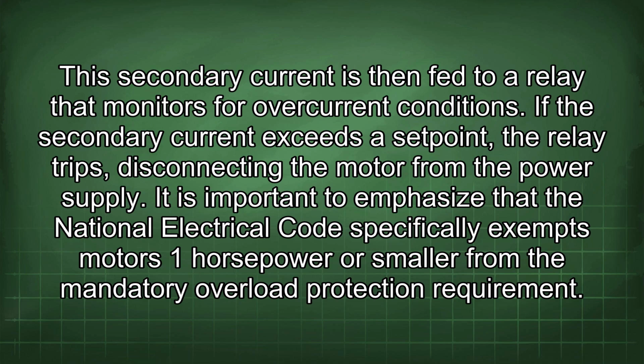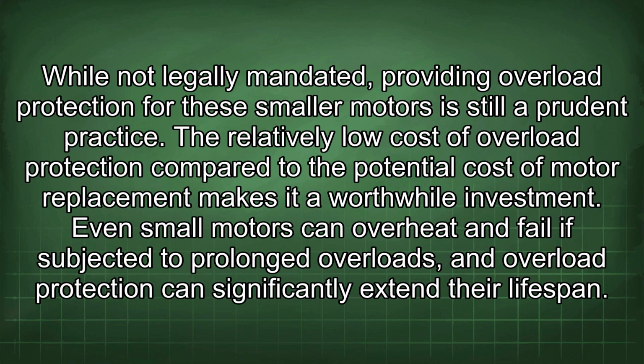It is important to emphasize that the National Electrical Code specifically exempts motors 1 horsepower or smaller from the mandatory overload protection requirement. While not legally mandated, providing overload protection for these smaller motors is still a prudent practice. The relatively low cost of overload protection compared to the potential cost of motor replacement makes it a worthwhile investment. Even small motors can overheat and fail if subjected to prolonged overloads, and overload protection can significantly extend their lifespan.